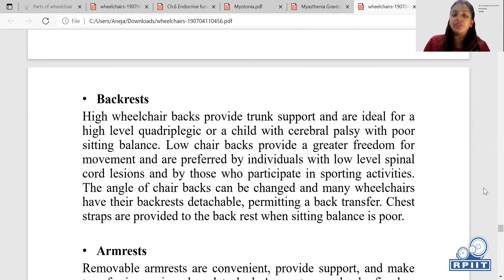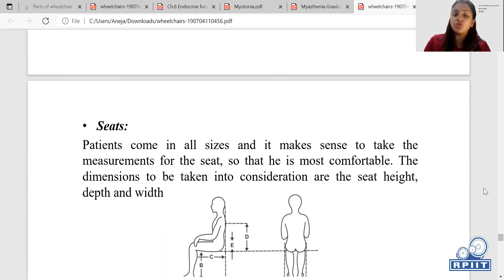Seats. So for the prescription of which seat to be given on the wheelchair, this depends on the person's or patient's assessment. Patients come in all sizes. It makes sense to take the measurement for the seat so that he is most comfortable. So dimensions to be taken into consideration are the seat height, depth, and width. For the seat width, first we have to measure the width of the widest part of the buttocks and then add 1 inch. For seat height, distance should be measured from the bottom of the heel to the popliteal area and 2 inches higher than that distance.